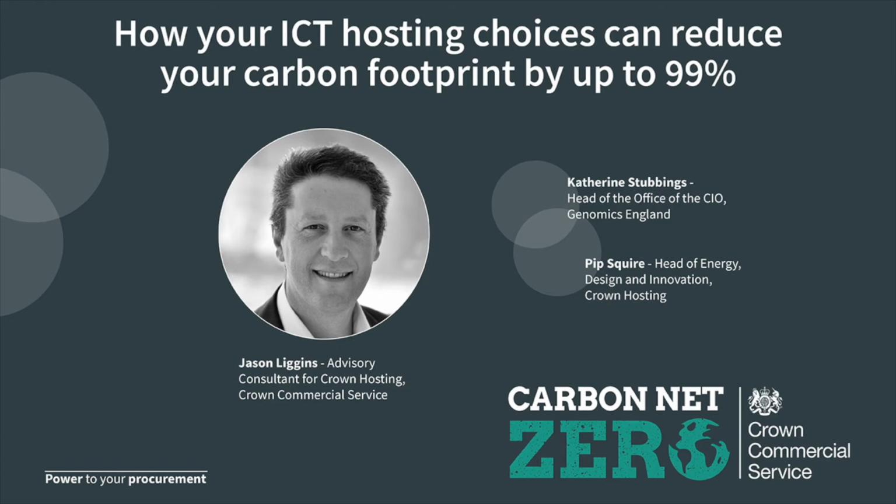What can we do with our customers? So that's to talk with people like Kat and their teams and ensure that they are really using strict hot and cold aisle containment. So there's no seepage of cold air into the warm zone. Basically, we're using all the cold air that we produce to cool the equipment. But also, if we can get customers to operate their equipment typically up around the 28 degrees C rather than historical 24, then there comes a point where we don't actually need any mechanical cooling at all for backup or hot weather, or anything like that.